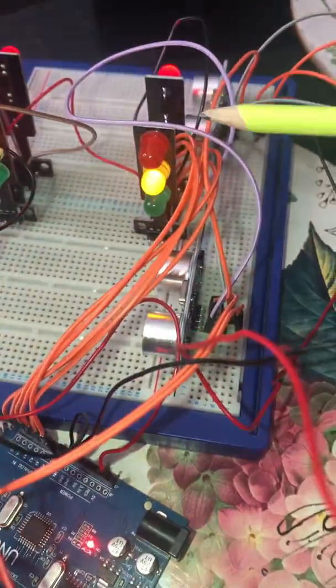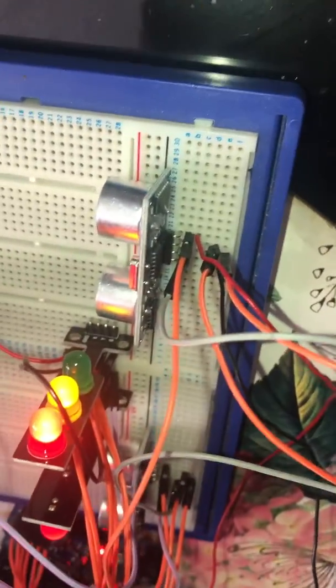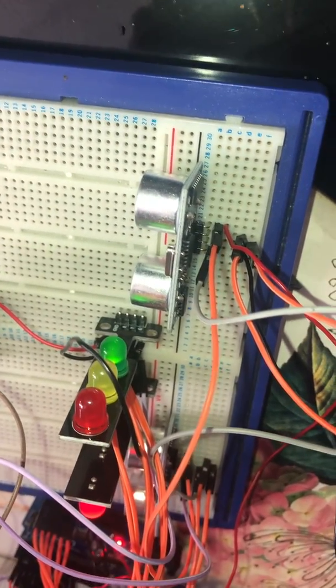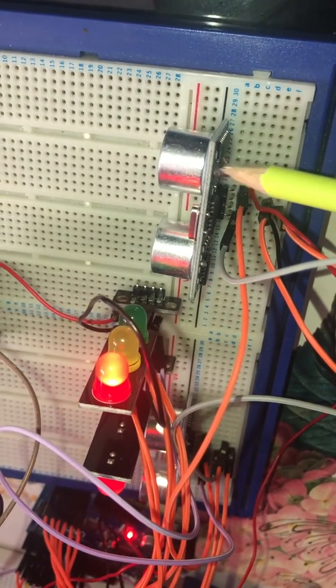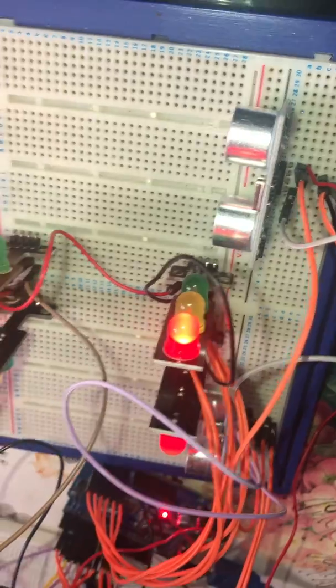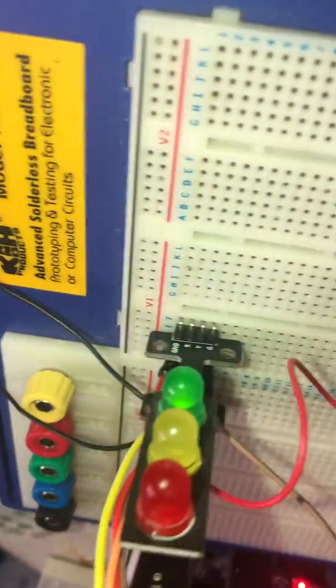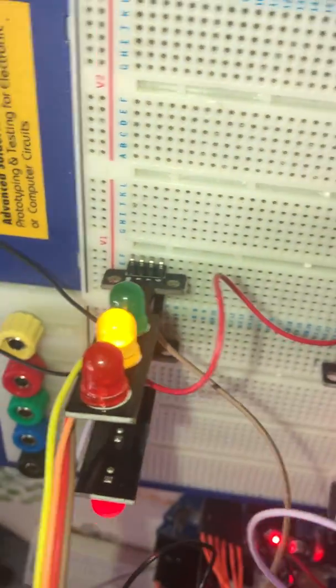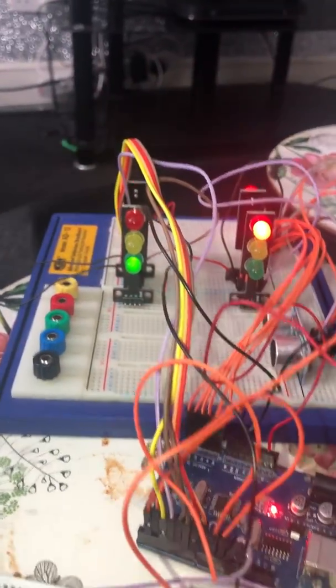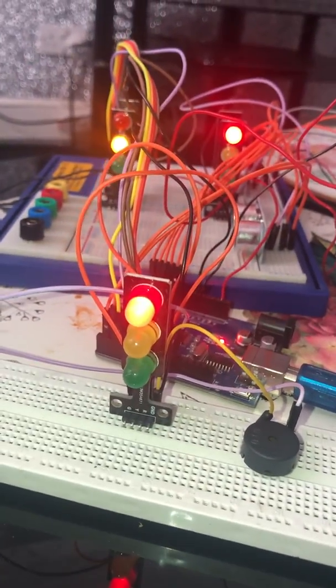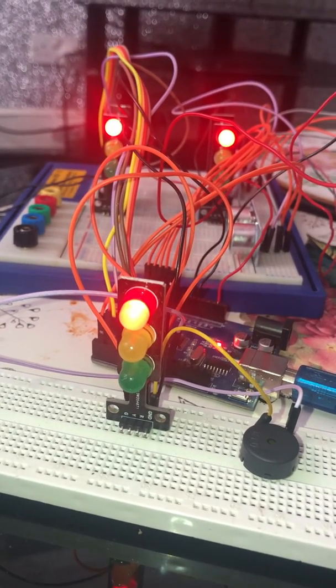I have already connected this thing. Then compiling done. It has started the sequence from lane 1. Red, to go back to this lane 2. This sensor is installed there, but it is not connected to any one of that. Then it goes to lane 3, green, amber and red. It goes back to lane 4, and then after that comes here to the pedestrian crossing.